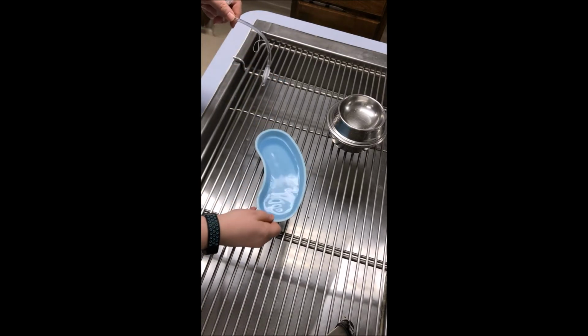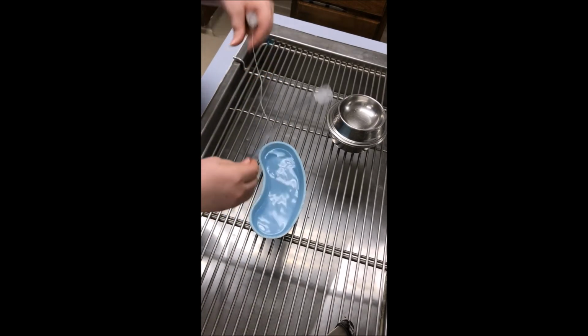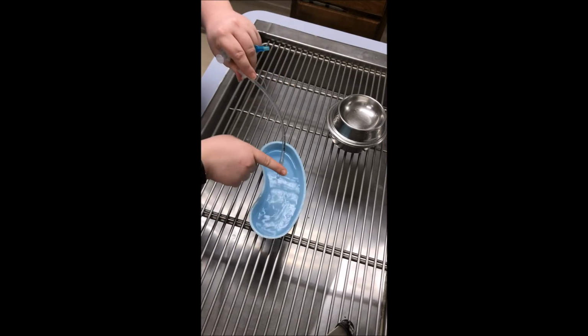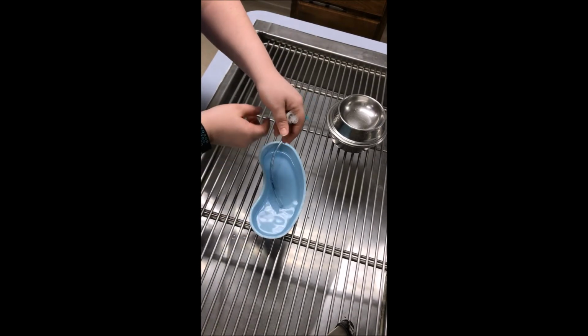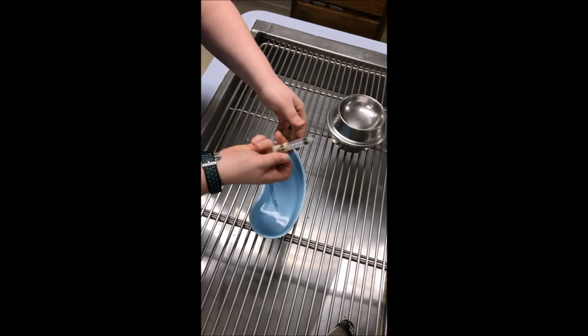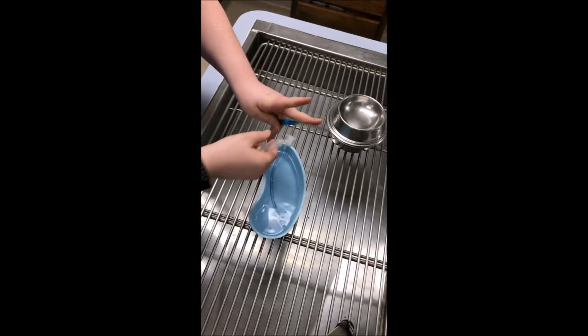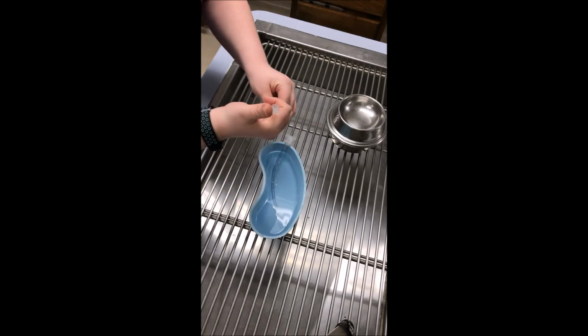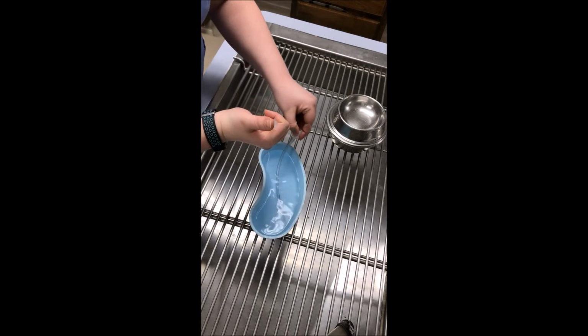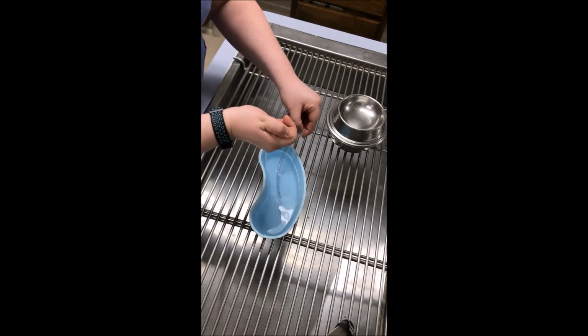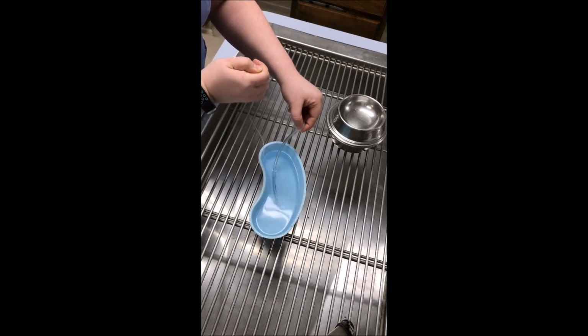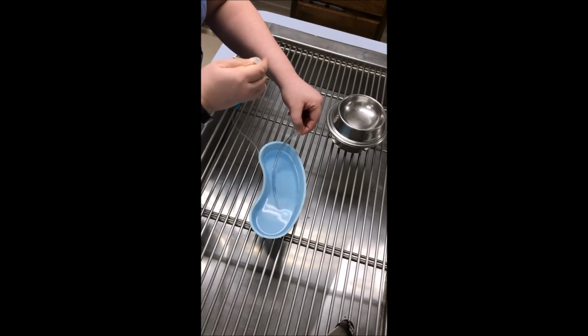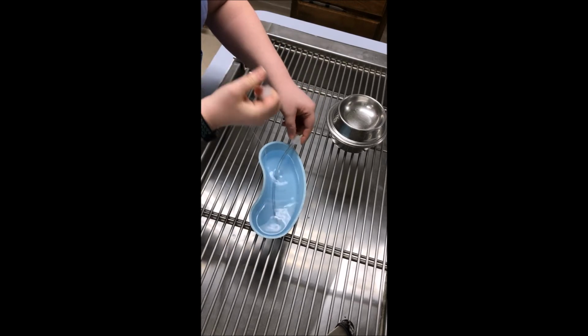We're going to take a container of water, submerge the tube with the cuff into the water. We have syringes that we mark to inflate the cuff, and then we're going to inflate the cuff and watch for any air bubbles to come up around the cuff, which would indicate a leak. If there were any air bubbles coming out, which there are none, then we would discard this tube and test a new one.